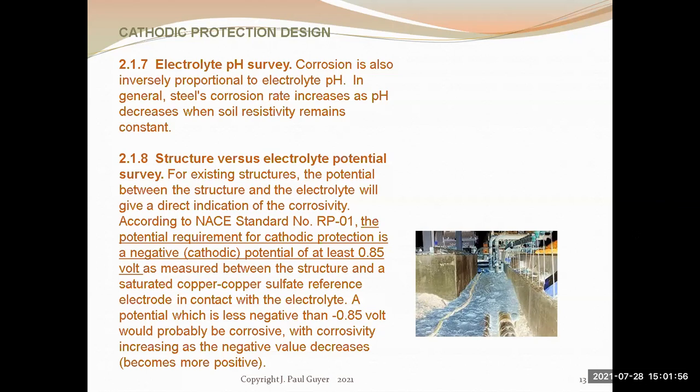Well, I didn't do a good job of clarifying this when I was talking about it. There is the soil resistivity test, the testing that you do as part of your field work, and you do that when you have a new structure being put in the ground, or if you have an existing structure. The other test that can only be undertaken as field work is the structure to electrolyte potential survey, and that can only be done if the structure is existing out there in the ground.